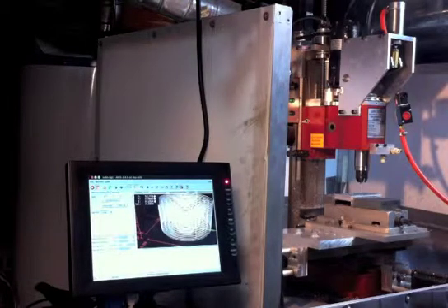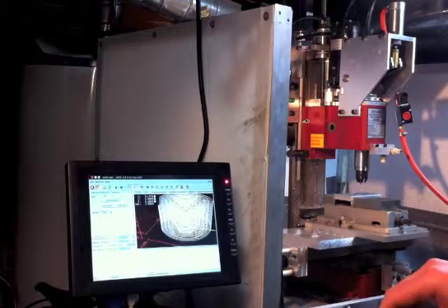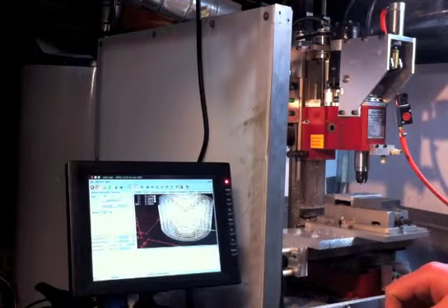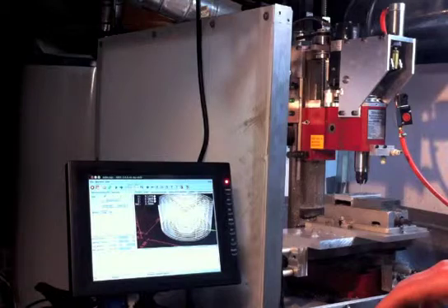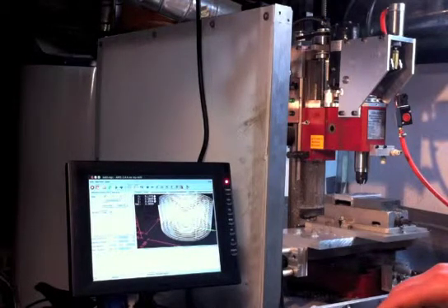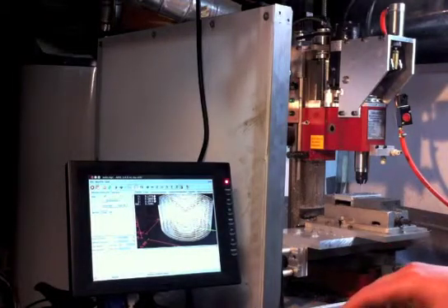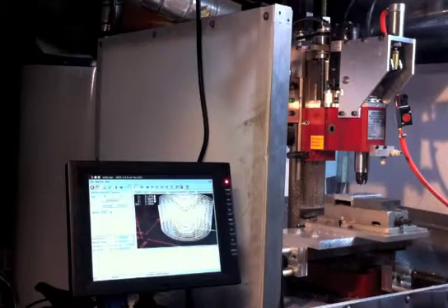And then when it comes time to do a touch off, if we want to go all the way down to 1/1000th, this makes it really easy to move the axes one stepper motor pulse at a time. And since this machine has a 2-to-1 reduction there, we're only getting 5/10000ths of an inch, or 0.5 thou per click there. Makes it very easy to get in, really sneak up on things in a very precise way.